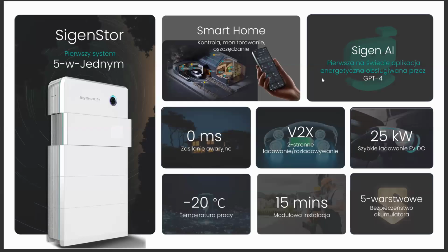But what really makes a difference for installers is the number of MPPT trackers. 10, 12, and 15 kilowatts units feature 3 independent MPPT trackers. 17 to 30 kilowatts models feature 4 MPPT trackers. What does this mean in practice?